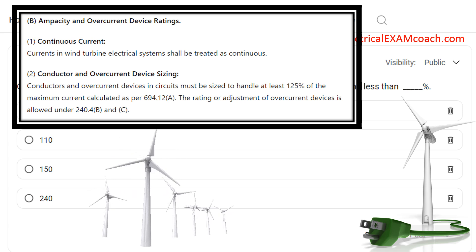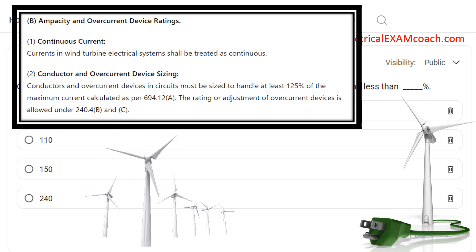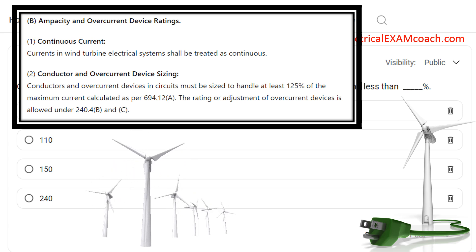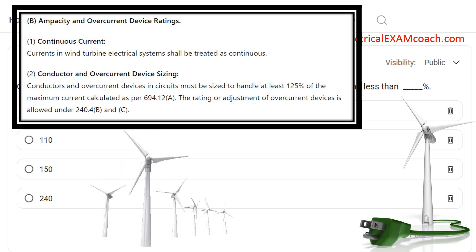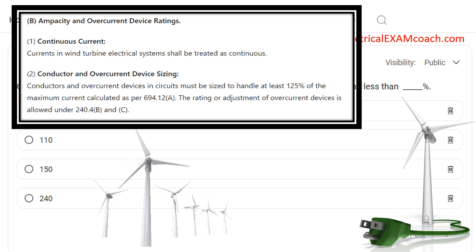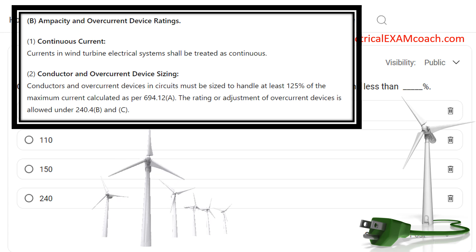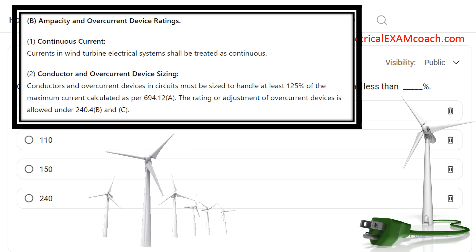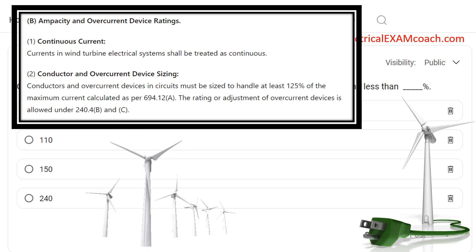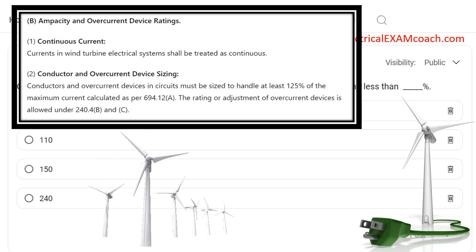When we get to 694.12(B) in part 1, it lets us know that currents in wind turbine electrical systems shall be treated as continuous. As we've learned in previous parts of the code, that typically means that we're going to multiply them by 125%. Then in part 2, it removes all doubt — it says conductors and overcurrent devices must be sized to handle at least 125% of the maximum current calculated in 694.12(A), which tells you how to calculate these currents.